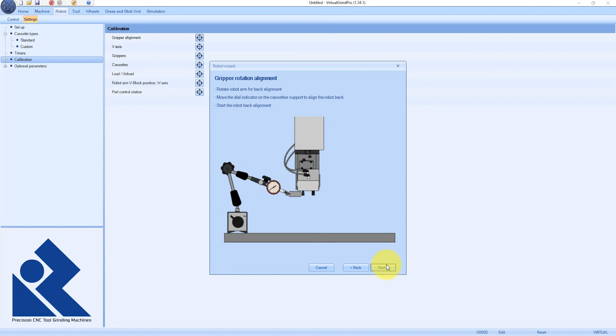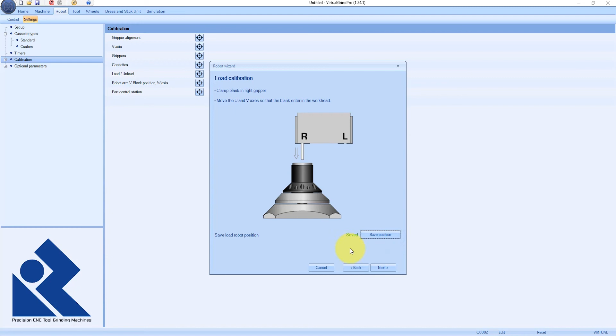Once finished, pressing finish means the value is taken into account on the machine. We can do the same thing here, with explanations showing what needs to be done. We save the position, and it tells us when it's saved. When we press cancel, it asks if we're certain we want to cancel. This way we can calibrate the whole cassette.